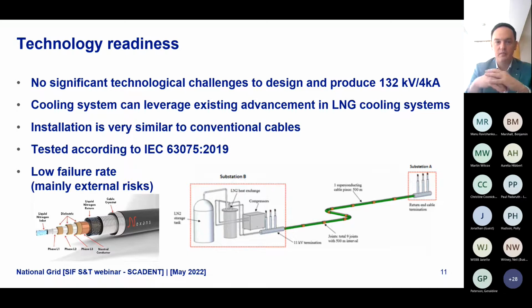Installation of the cable itself is quite similar to a conventional cable. It has very similar dimensions to a 132 kV cable. It's a bit more challenging to install the joints, but they run in 500 meter sections. So for the 5 to 10 kilometer systems normally used in distribution networks, we don't need as many joints, and obviously the termination looks a bit different, as well as we need the cooling system.